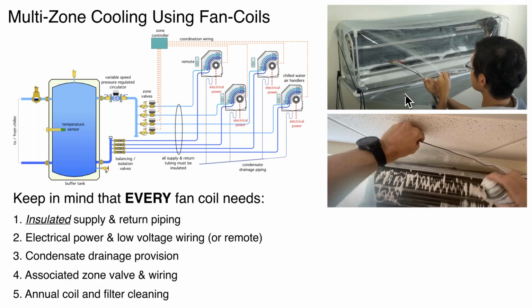You might want to consider a single zone cooling as opposed to a multi-zone cooling. And really, I would tell people, if you're looking at multi-zone cooling, I really want to hear, how are you going to use it and why do you want multi-zones? You know, if it's, I want to keep this room at 75, I want to keep that room at 76, and I want to keep another room at 72, I'm going to try to talk you out of multi-zone cooling.